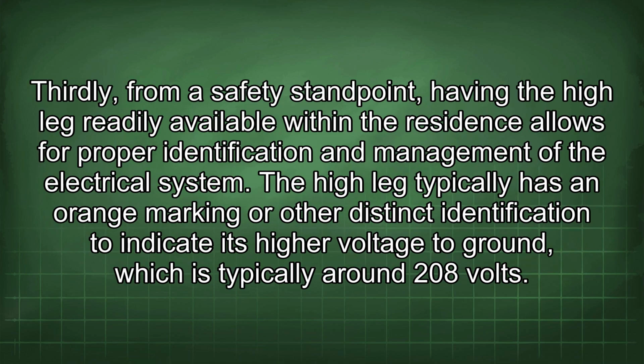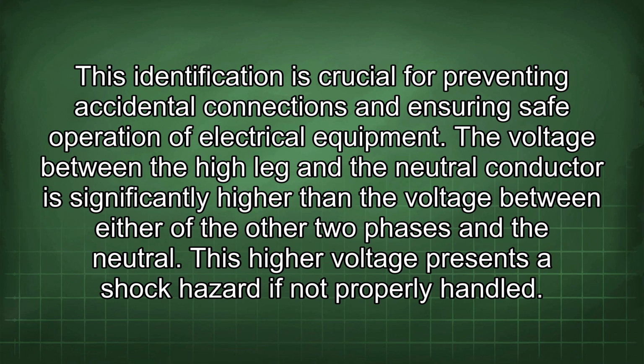Thirdly, from a safety standpoint, having the high leg readily available within the residence allows for proper identification and management of the electrical system. The high leg typically has an orange marking or other distinct identification to indicate its higher voltage to ground, which is typically around 208 volts. This identification is crucial for preventing accidental connections and ensuring safe operation of electrical equipment. The voltage between the high leg and the neutral conductor is significantly higher than the voltage between either of the other two phases and the neutral. This higher voltage presents a shock hazard if not properly handled.